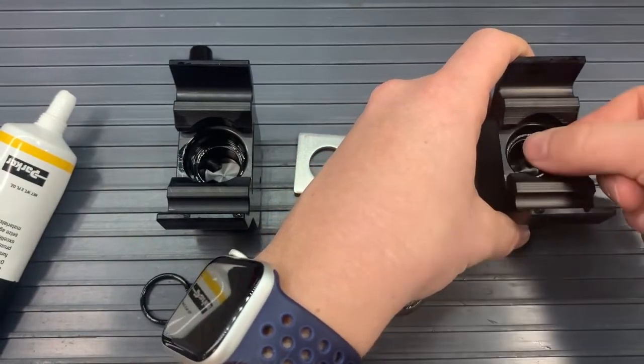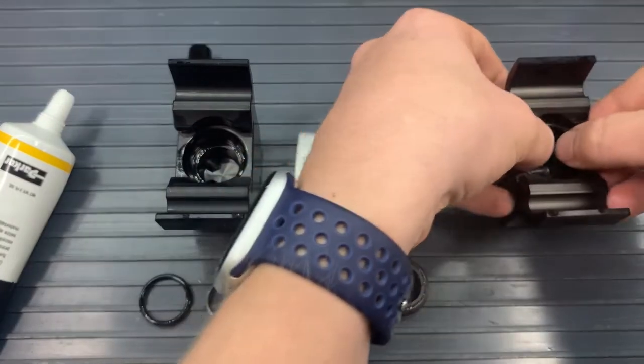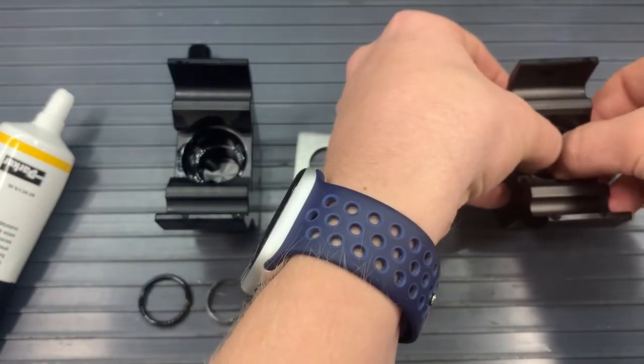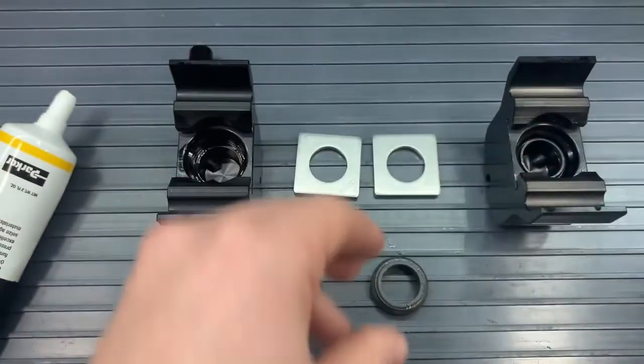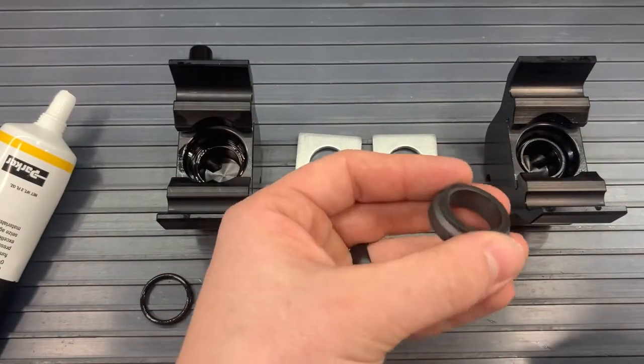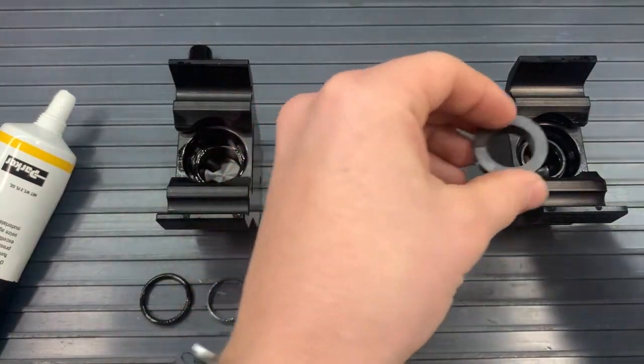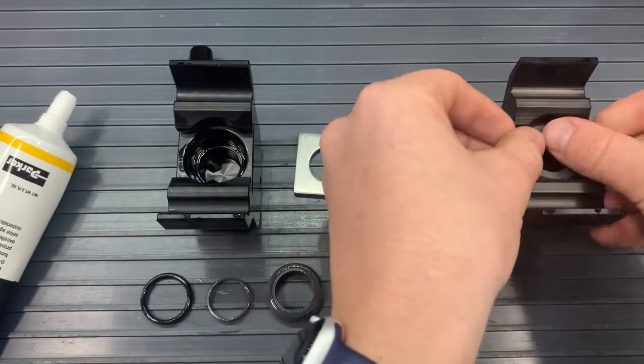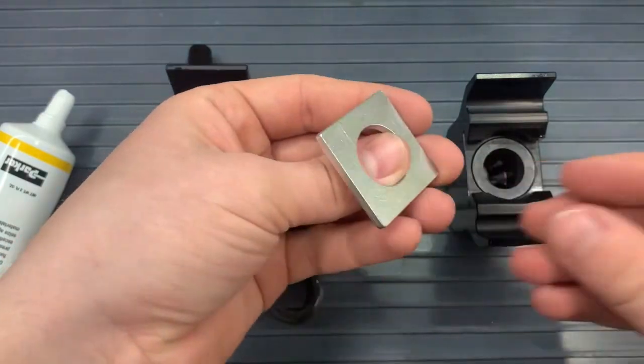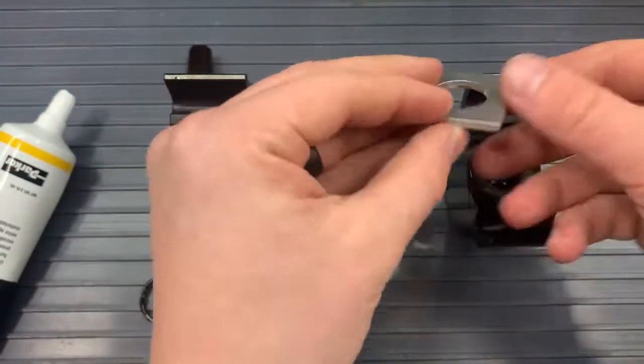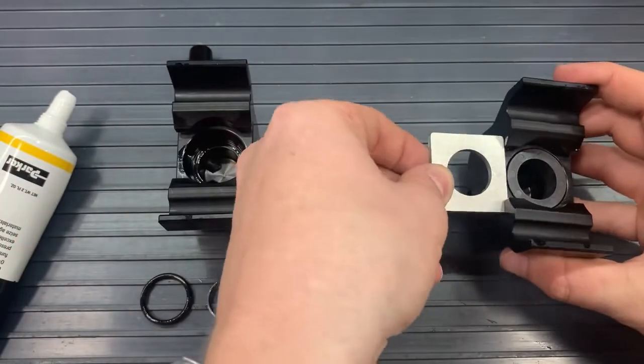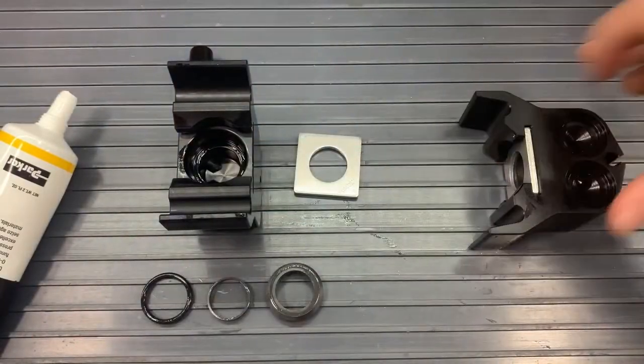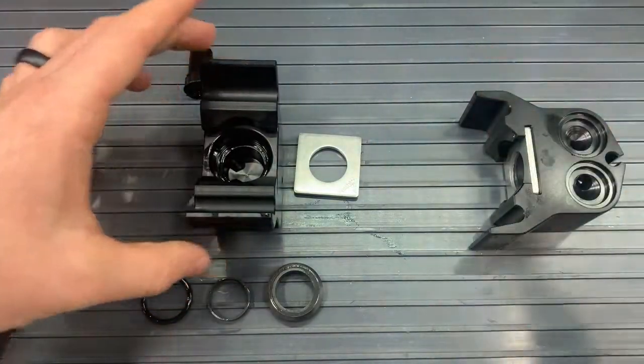Once we have the O-ring in there, we'll now get the seal ring and center it on that O-ring. Once the O-ring and seal ring are in there together, we will grab our plunger guide and orient it like so, and push it down until you hear almost a click. That means that the seal ring is within the O-ring and they're all sitting flush with that seal bore opening. With those 3 pieces sitting inside the seal bore of the pump head, we can now put the retaining plate to cover the 3 pieces so that it won't fall out.